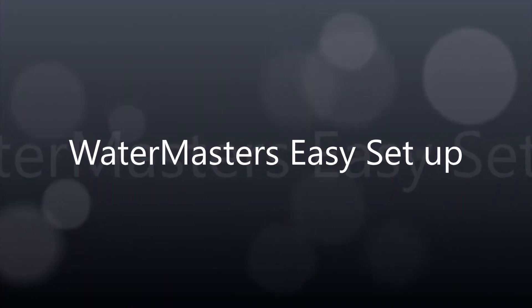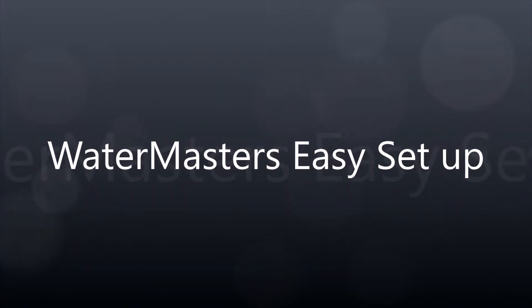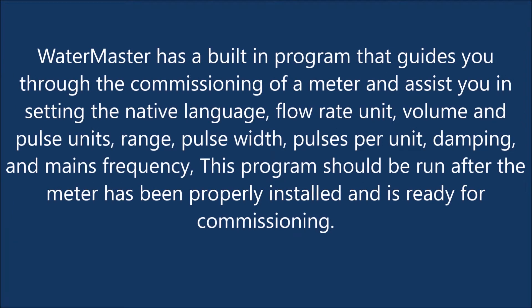Water Master Easy Setup. Water Master has a built-in program that guides you through the commissioning of a meter and assists you in setting the native language, flow rate unit, volume and pulse units, range, pulse width, pulses per unit, damping, and mains frequency. This program should be run after the meter has been properly installed and is ready for commissioning.